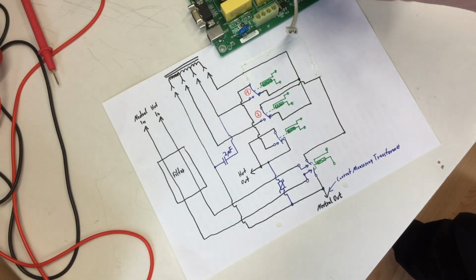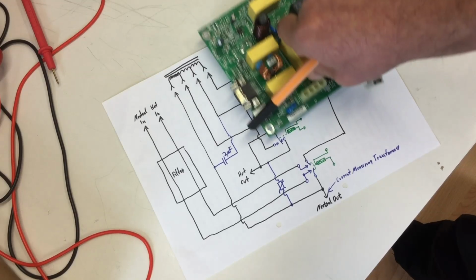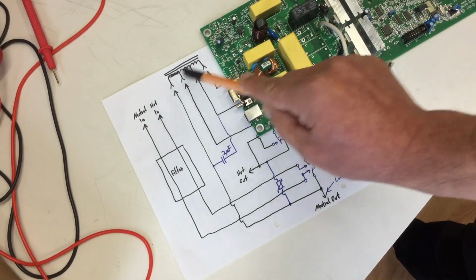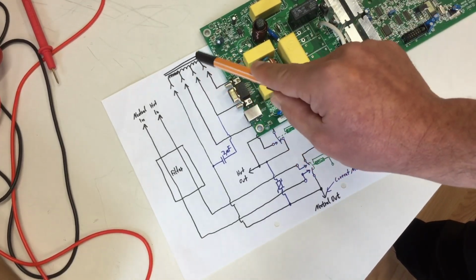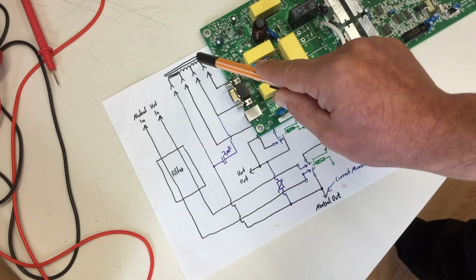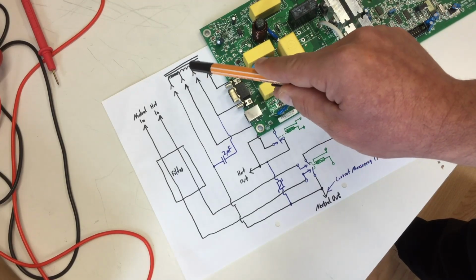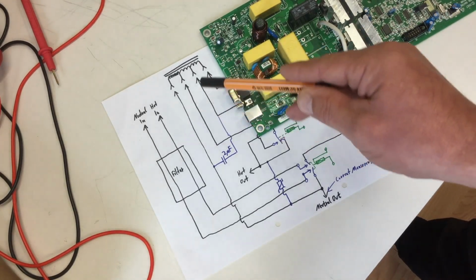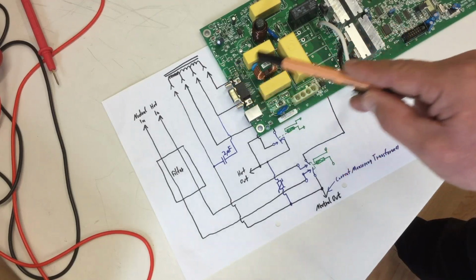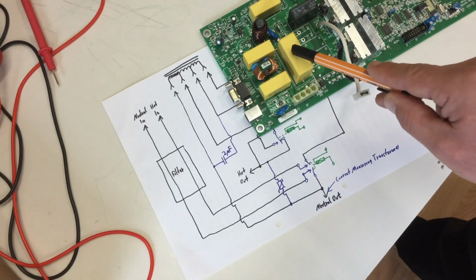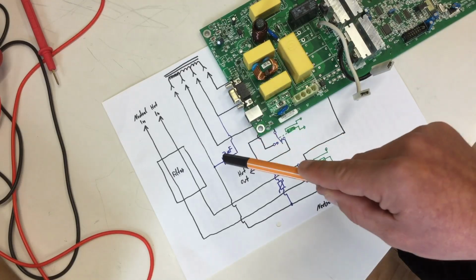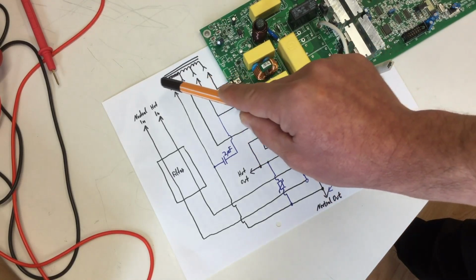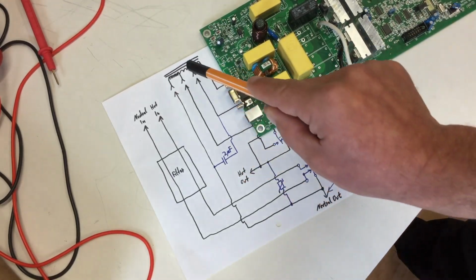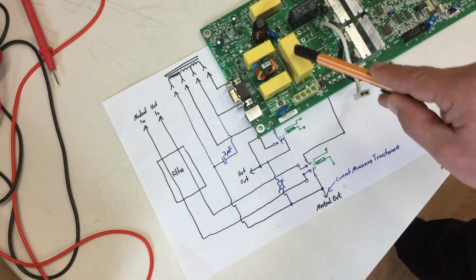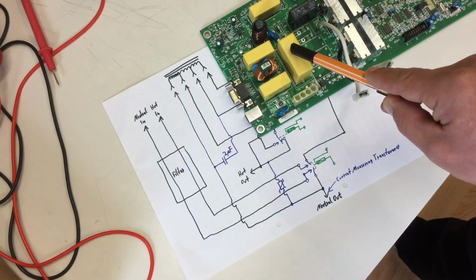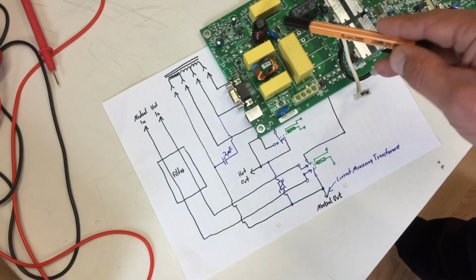If the thing is doing nothing, the transformer is basically a big inductivity between live and neutral, and that would totally distort the power factor. That's what this capacitor is for, 2 microfarad, parallel to the windings of the transformer. That should correct the power factor somehow, a cheap way to do it, the easiest way.